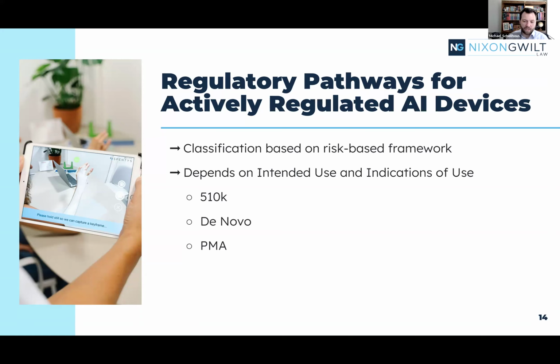Well, the FDA often requires clinical data when the technological differences are significant, or when non-clinical testing methods are limited or inadequate for the FDA to be able to confirm whether the safety and effectiveness of the devices are sufficient. With AI-enabled products, we are often seeing the FDA require clinical data because the technological differences are significant from their viewpoint from the previous predicate devices, which are a very different method of achieving the same intended use. That doesn't mean that clinical data is always going to be required. It is going to be a very case-by-case basis and depend on exactly what, again, going back to those big three, what you're doing, who you're doing it for, and importantly, how you're doing it. But it is something to keep in mind, and you're always going to have to look at the details.